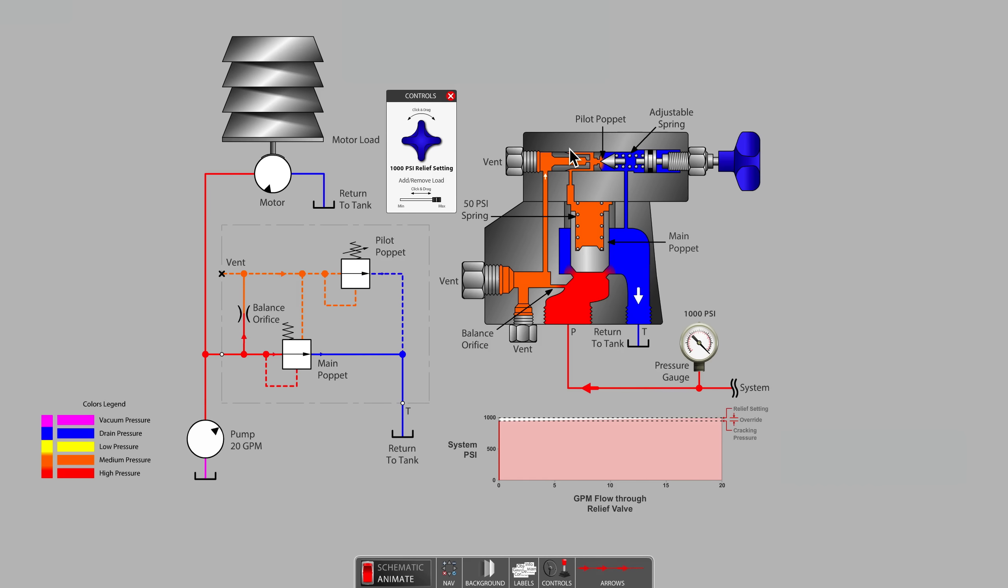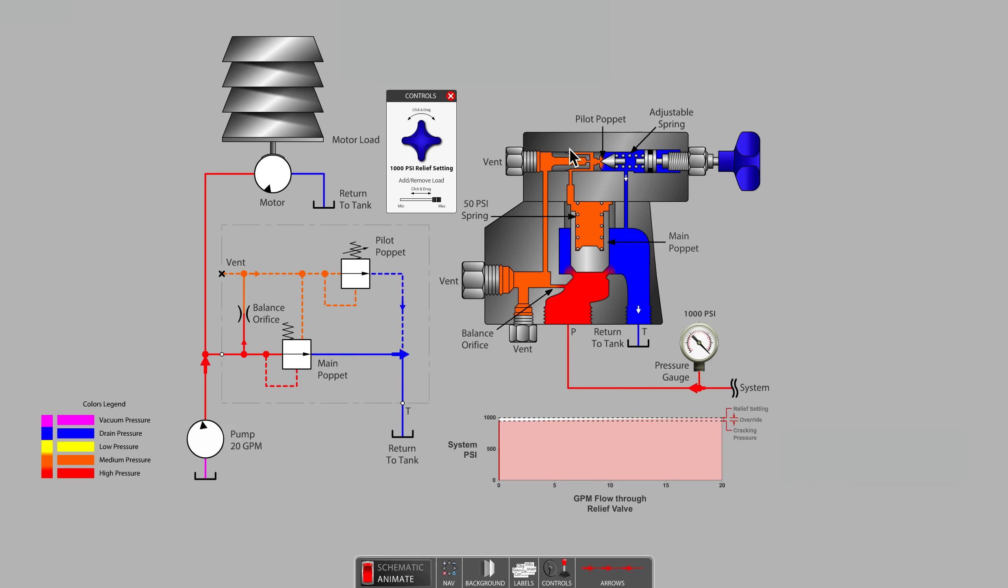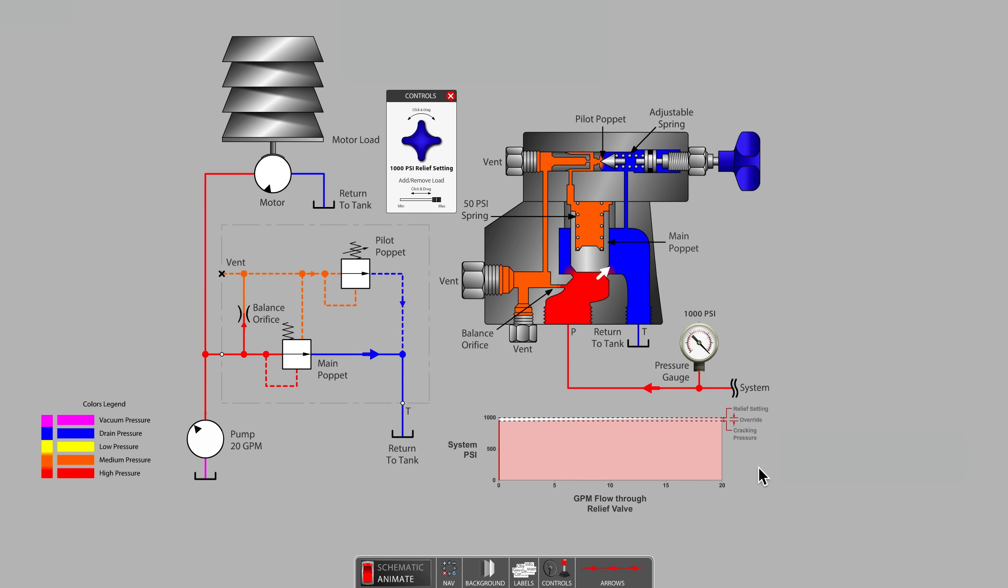Unlike a direct acting relief valve, where the cracking pressure and full flow relief setting pressure may be several hundred PSI apart, the balanced style pilot operated relief valve has a very narrow pressure override band.